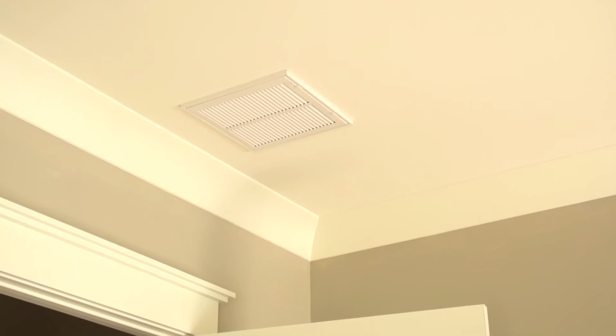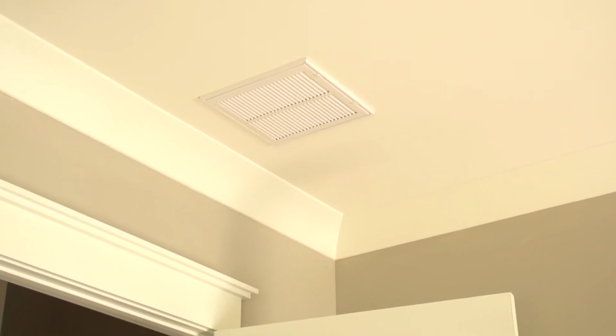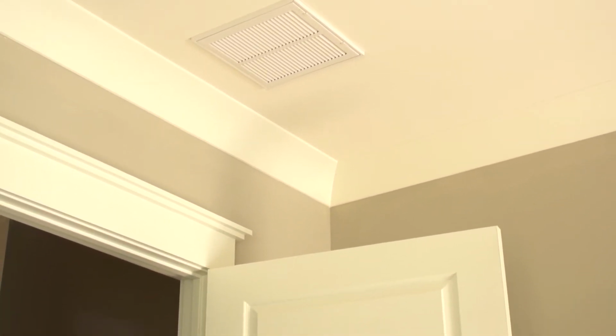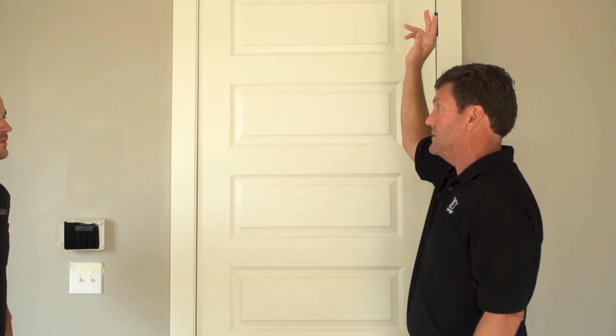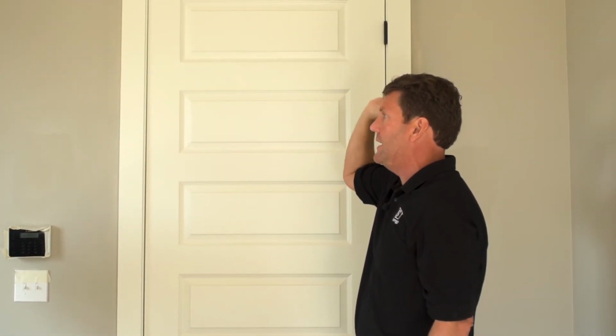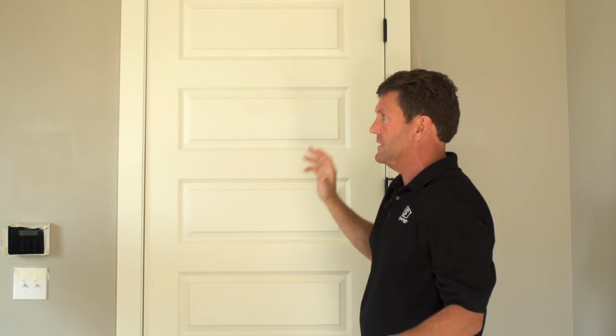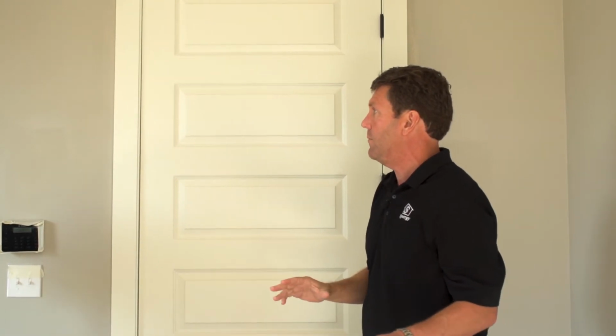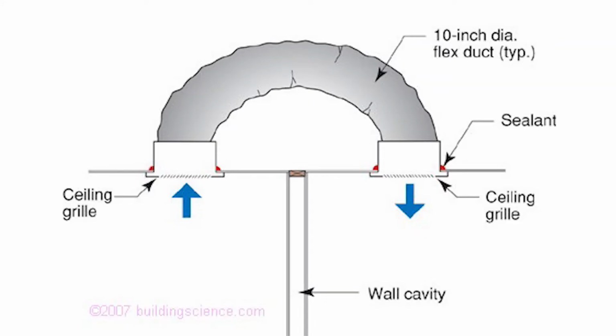The simple solution is to put either a return or a jumper duct in each bedroom. A lot of people don't care to have these extra grills in their house, but that's the difference between a room getting cool and being comfortable. A jumper duct isn't supplying any air from the unit directly; it's not a direct path back to the unit. All you're doing is basically equalizing the two rooms.